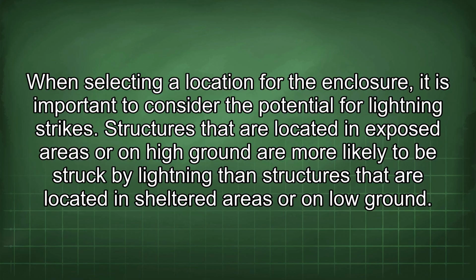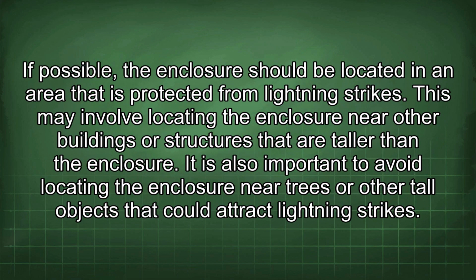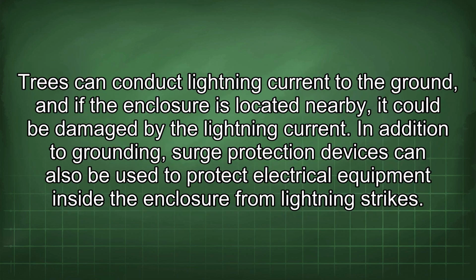Structures that are located in exposed areas or on high ground are more likely to be struck by lightning than structures that are located in sheltered areas or on low ground. If possible, the enclosure should be located in an area that is protected from lightning strikes. This may involve locating the enclosure near other buildings or structures that are taller than the enclosure. It is also important to avoid locating the enclosure near trees or other tall objects that could attract lightning strikes.